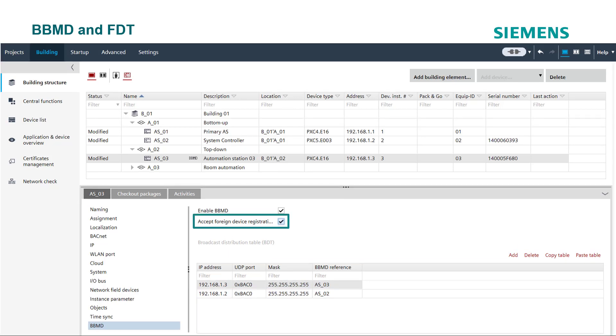To allow foreign device registrations, click on this checkbox. This allows a device to register with a BBMD, join a BACnet IP network, and send its broadcast messages to the BBMD. The related checks are done in the network check task.